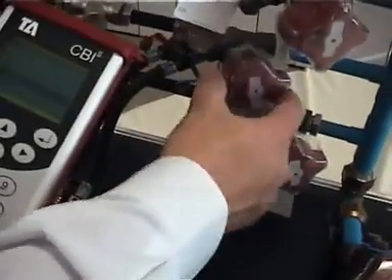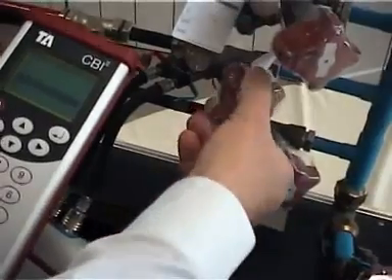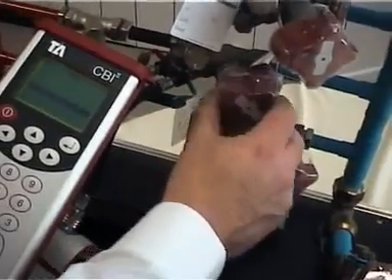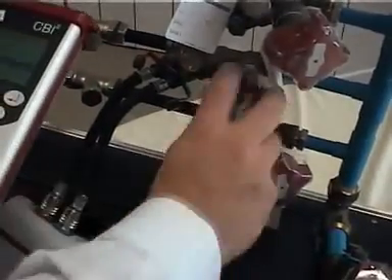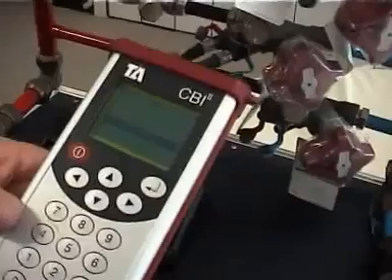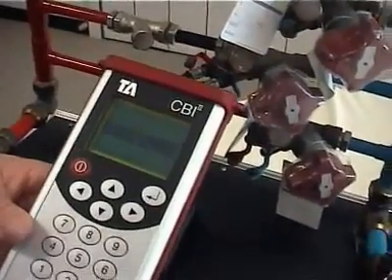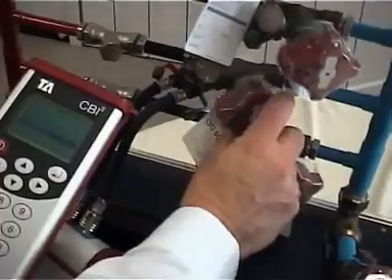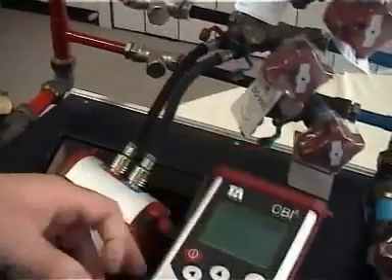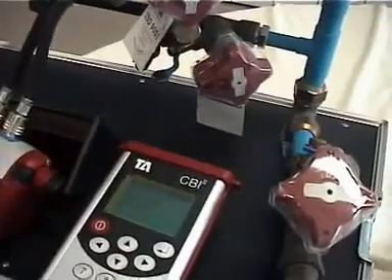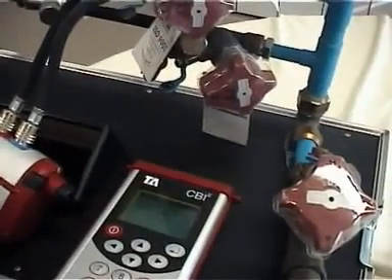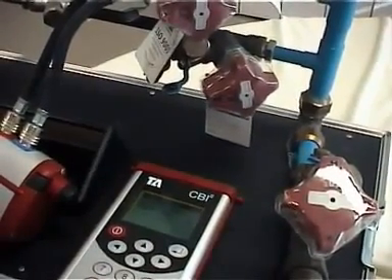It tells us that we have to shut our valve again. Close our valve. Press enter. It tells us our differential pressure at closed valve. Open the valve back up to the two turns. Press enter. And it tells us that we're going to move on to the next valve. We do that for the number of valves that we have decided in our module that we're going to calibrate today.